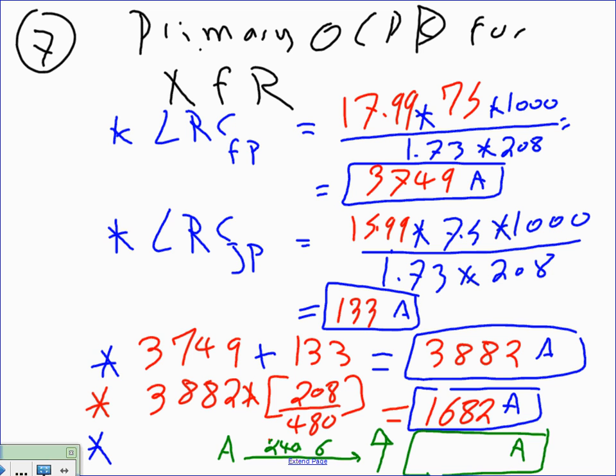Now, you take yourself to 1,682 amps. Now we're going to size based on 240.6(A). I can't emphasize this enough. You take the 1,682, guys, and use 240.6(A). The standard ratings are non-adjustable. If they're adjustable, Nick, then you can use the long time pickup and tweak it down to get you 1,682. Cool. But since they're not adjustable, you have to go up to the next standard. What's the next standard? 2000.